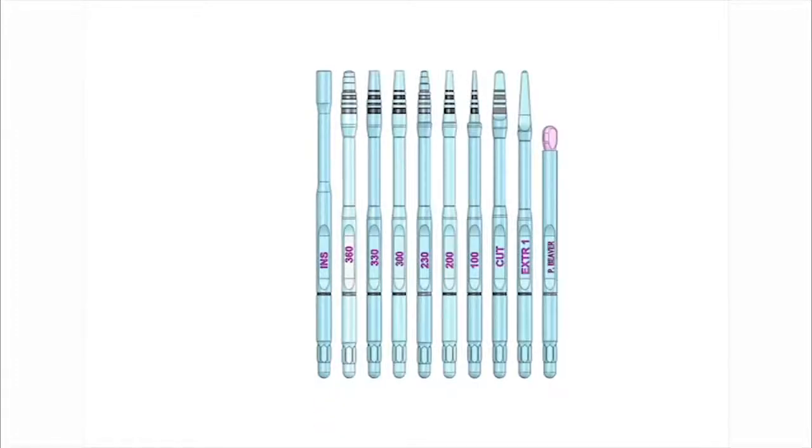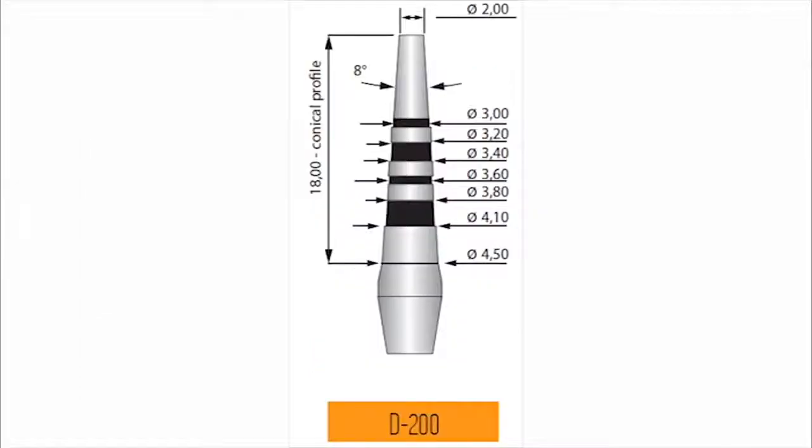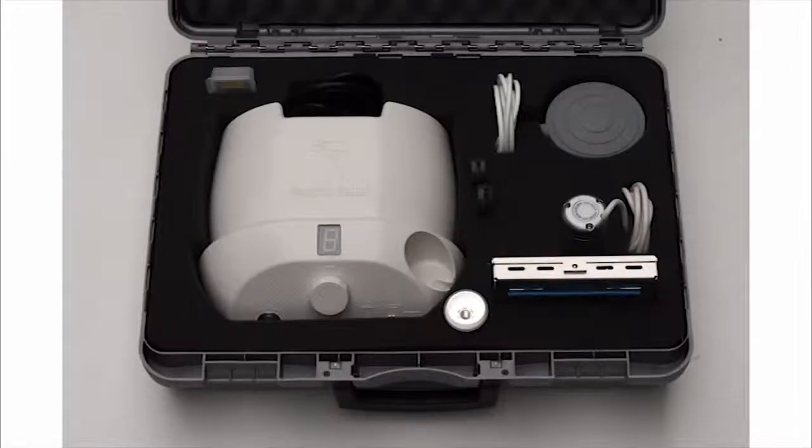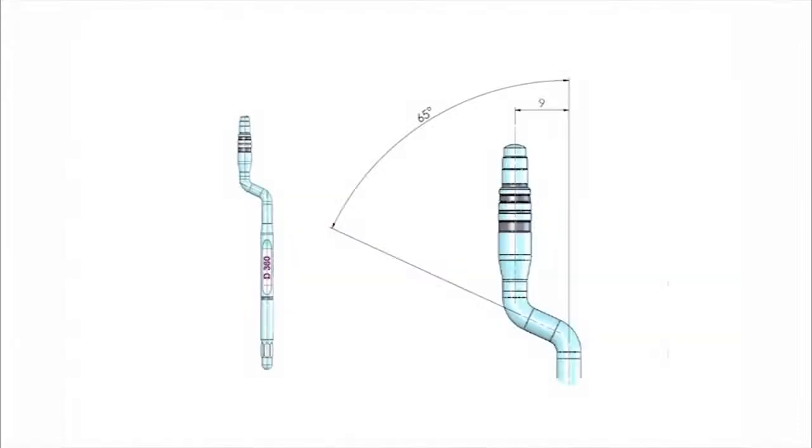All the surgical instruments, except for the beaver and the extractor, are laser marked to show the difference in depth. This will make the check easier during the surgery practice. The standard kit also includes one spare silicone cap with one spare ring nut, two wrenches, a container with two blades, and an instruction for manual use. But there are tools on demand too.